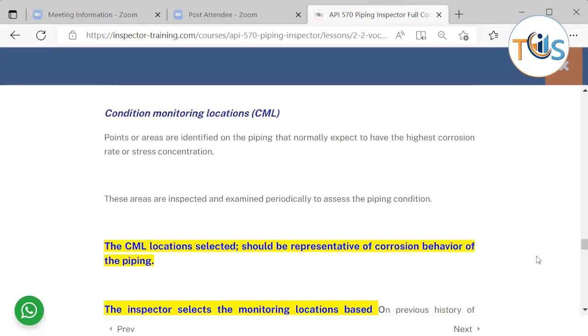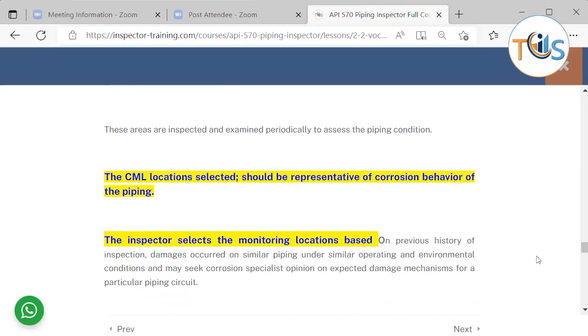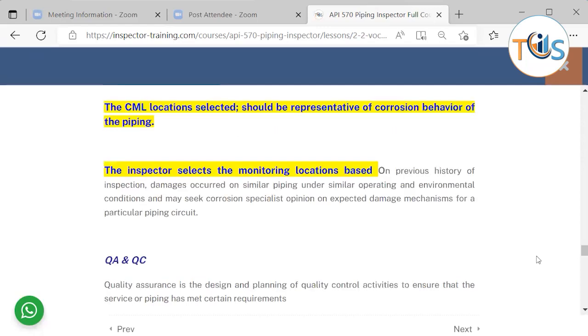Conditioning monitoring locations are areas on the piping where you measure thickness and corrosion, using previous measurements as a benchmark for comparison. You identify areas where you expect the highest corrosion rate or stress concentration — the weakest link — and keep monitoring that location to determine corrosion rates. CML locations are normally selected by the inspector and should be representative of the corrosion behavior of the piping. They should be practical and accessible, selected based on previous inspection history, damage occurrence, or similar piping under similar operating and environmental conditions.